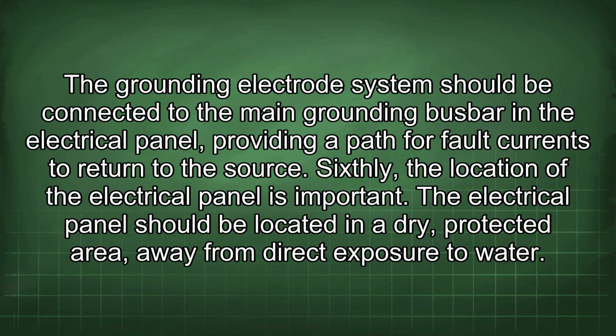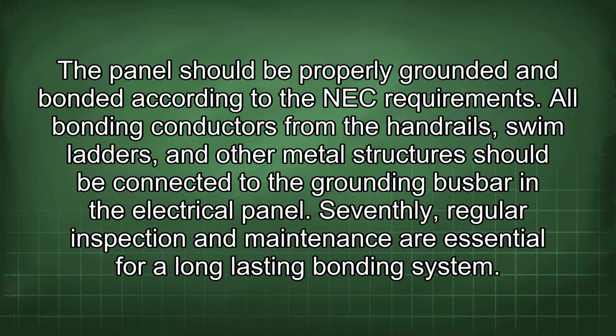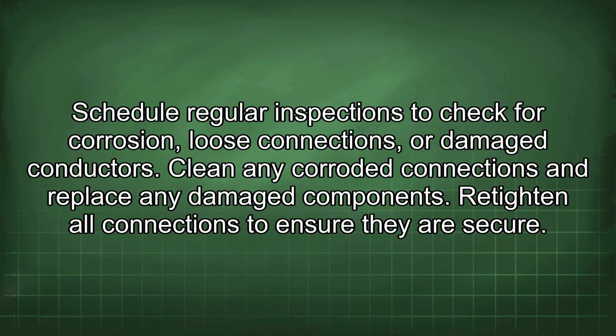Sixthly, the location of the electrical panel is important. The electrical panel should be located in a dry, protected area away from direct exposure to water. The panel should be properly grounded and bonded according to the NEC requirements. All bonding conductors from the handrails, swim ladders, and other metal structures should be connected to the grounding busbar in the electrical panel. Seventhly, regular inspection and maintenance are essential for a long-lasting bonding system. Schedule regular inspections to check for corrosion, loose connections, or damaged conductors. Clean any corroded connections and replace any damaged components.